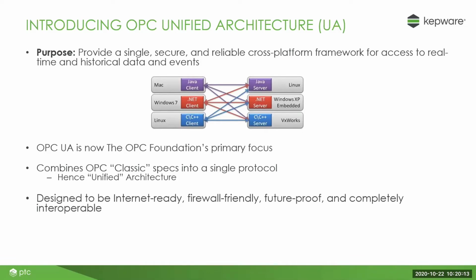The next key thing is that in traditional classic OPC DA, they are not firewall friendly. If you're using a firewall or antivirus, it will be very challenging to do an OPC remote connection, because classic OPC is based on RPC calls. What actually happens is when you initiate an OPC remote connection, it does a port 135 connection to the other side, and then gets back a high port which is randomly assigned. That's the key problem that makes it firewall unfriendly, because the port for that connection session is randomly assigned across the high port range.